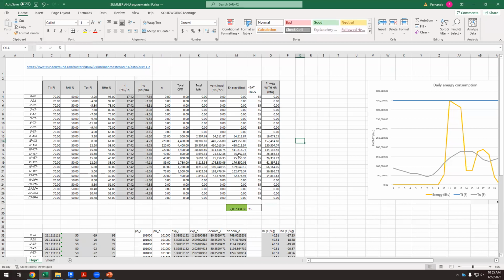Okay. So if I have 430,000 without the heat recovery, it's only 150,000 with it. So if the heat recovery is 65, I consume only 35%. Okay, so that's the idea. With the heat recovery, we can have huge savings. In this kind of building with a high occupancy, in a single family house with 2 or 3 people, it doesn't matter. But when we have hundreds of people, the heat recovery matters a lot. So this is mandatory, having heat recoveries in this kind of buildings.